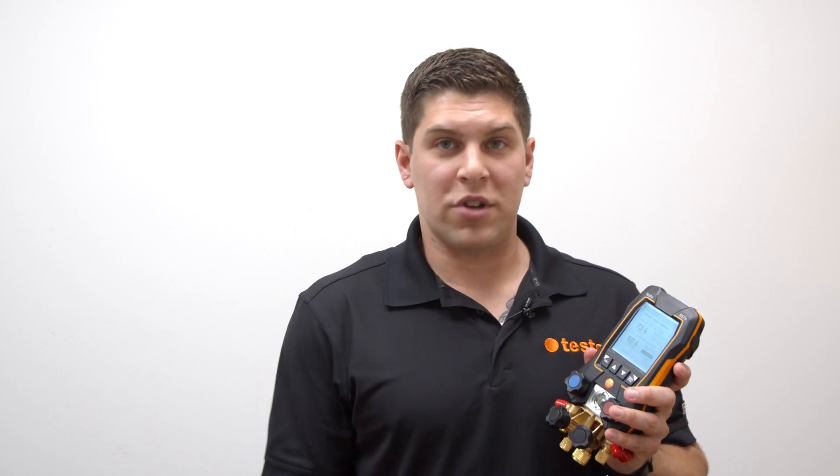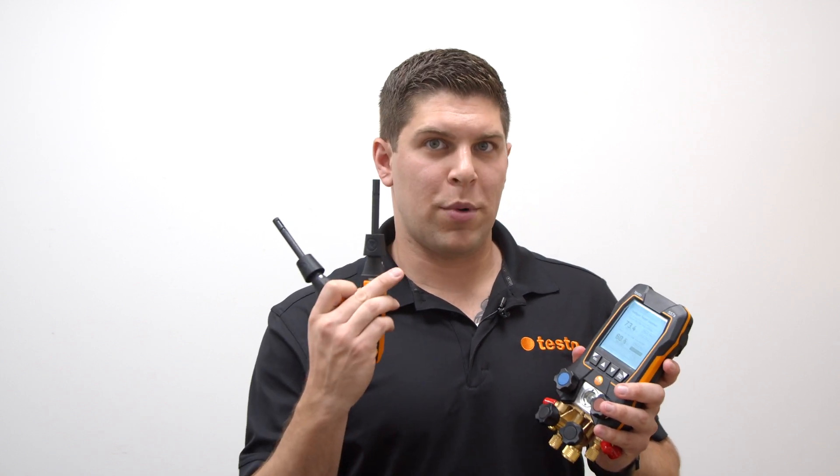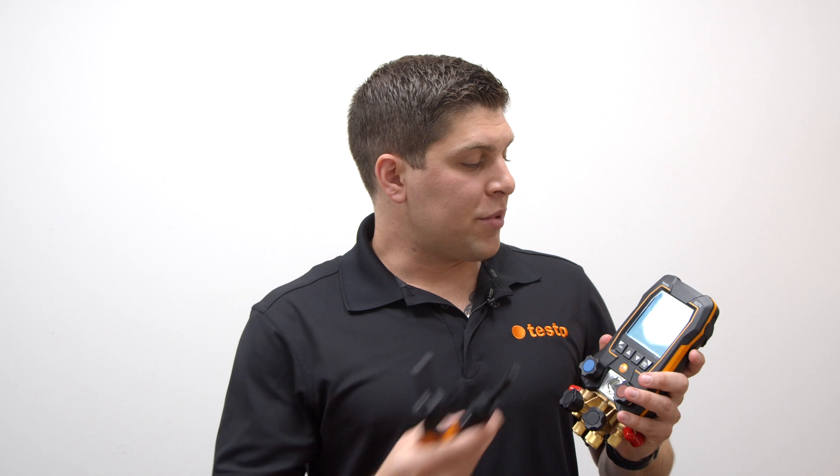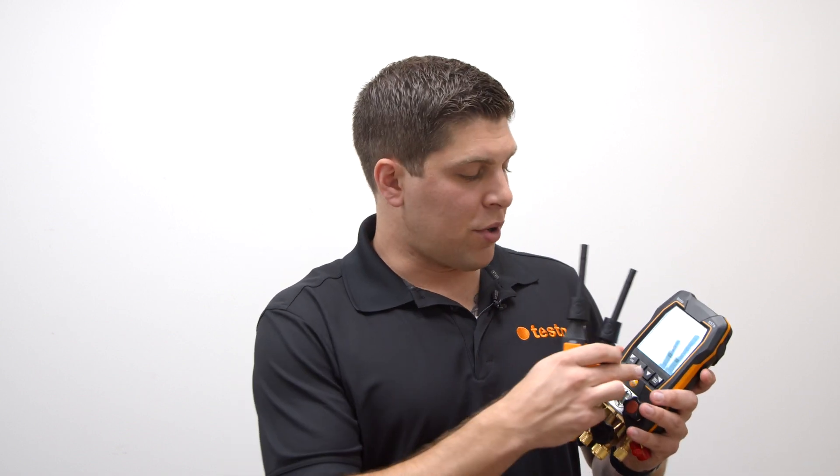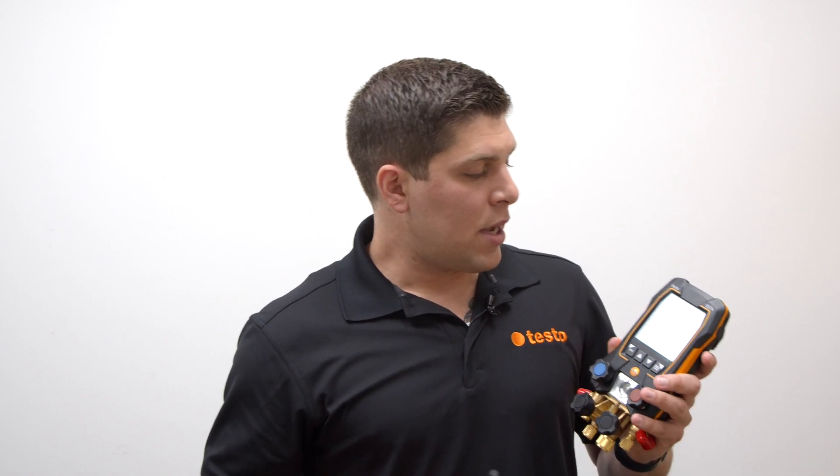Another measurement — and probably one of my favorites and most used for commissioning new systems, whether residential or commercial — is the target superheat mode. You'll need 115i's and 605i's. With Bluetooth 5.0, you can set your smart probes right at the beginning when you go into target superheat mode, or set them manually if you have other probes that can measure temperature.